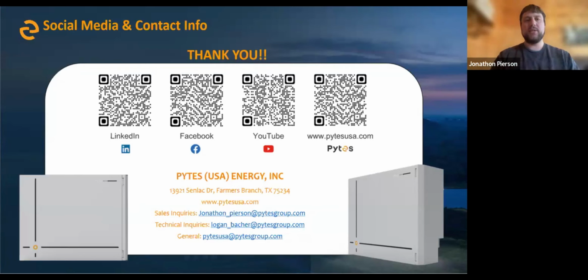Also, aerosol protection: now we have a fire extinguisher. When the BMS reaches 400 degrees Fahrenheit, we light that aerosol protection to ensure there is no more thermal runaway. This is an added feature, obviously with LFP chemistry, one of the safest chemistries on the market for energy storage, as an added layer of protection.